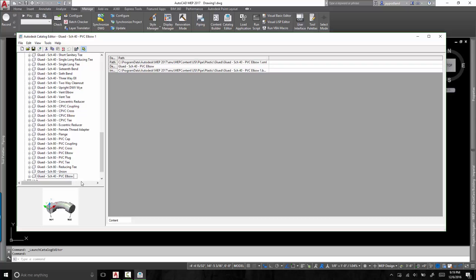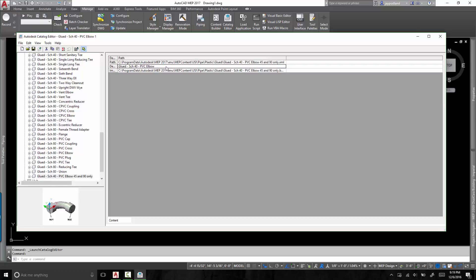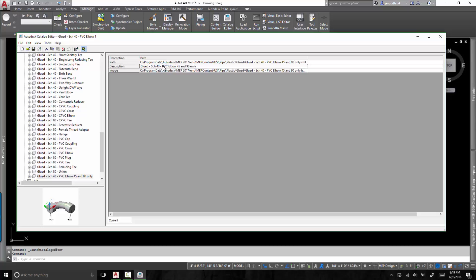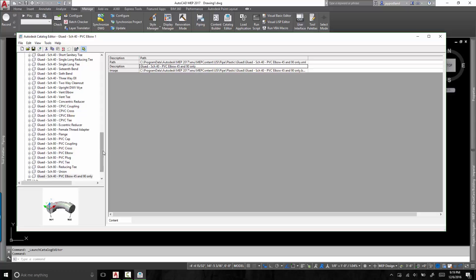And I will rename this one. I will rename it so it gives me the appropriate name here. So I'll tell it it's a 45 and 90 only. So these elbows are 45s and 90 only. Now what I'm doing here is I'm just selecting that line that I typed here. And I'm going to change it here in this description. As you can see, the description says glued dash schedule 40 dash PVC. Now this is important because the description is what actually shows up in the pipe routing preference. So I want to make sure that those two match.